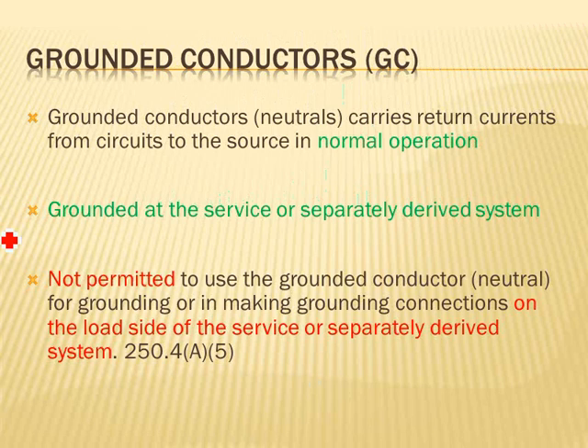The difference between the grounded conductor and everything else: the grounded conductor, the neutral guys, is an essential part of the normal operation of the power system. Essential part. If you are to utilize neutral voltages, line to ground voltage, 120 or 277, you must pull a grounded conductor. So yes, it's part of the grounding system, the grounded conductor, but it's really an essential part of the normal operation of the power system. So we talked about grounding in the service and similar systems. It's not permitted to use the grounded conductor, with some exceptions, as a grounding conductor.